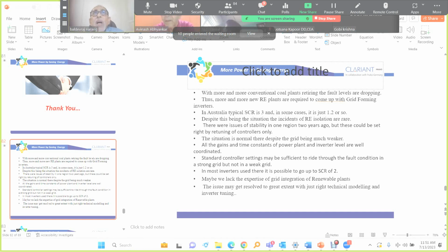Yes, sir, you're right, sir. What is happening is, in steady state condition, we have no issues. Steady state is perfectly okay anywhere, even at the remote and farthest locations. Anything works there. And during fault conditions at those locations, nothing works. The reason could be, as you said, the PLL controllers. If we design them properly and they are properly tuned, they are able to correct the situation, and it is okay. But if the situation is out of their hand, they will have to trip. They have to detect the fast changes of the fault and isolate. But if the PLL is not detecting, they are not tripping, they are still in the system but not doing anything. They are going into an oscillatory mode and all.